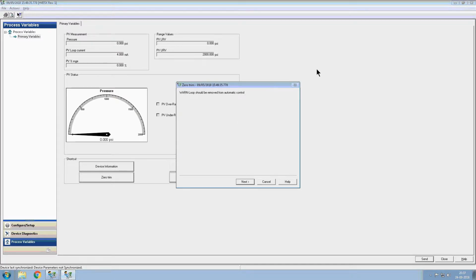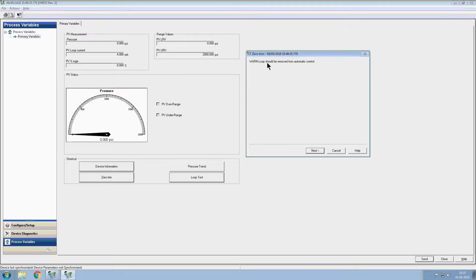Like any other method, the first screen is a warning message for the user to remove the device from automatic control. Press Next after the action is complete. The user is given a warning before starting the zero calibration, as this will affect the sensor calibration that is done at the factory. Press Next. This screen asks the user to apply the new zero to the sensor. Press Next after applying the zero pressure.